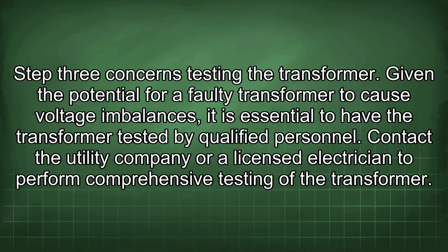Step 3 concerns testing the transformer. Given the potential for a faulty transformer to cause voltage imbalances, it is essential to have the transformer tested by qualified personnel. Contact the utility company or licensed electrician to perform comprehensive testing of the transformer.